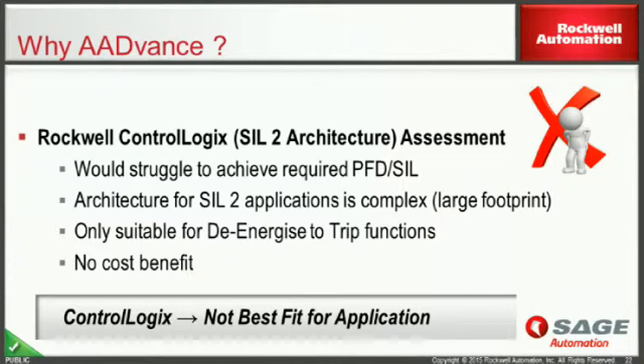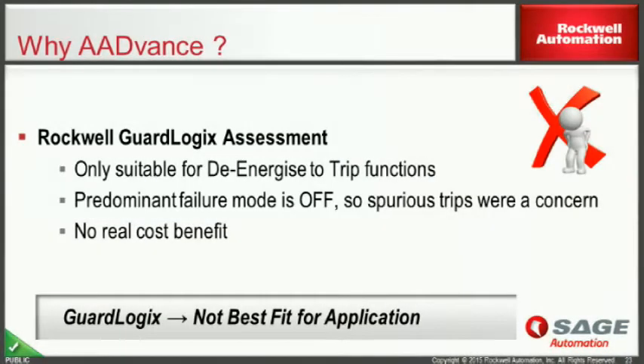And ControlLogix is only really suitable for de-energized to trip functions, and we have a couple of energized to trip functions within this system. So instead of failing to off, we needed to make sure that we maintained or energized a function to trigger a safety function. And there was no real cost benefit either in terms of hardware cost between AADvance and ControlLogix SIL2. The GuardLogix, again, it's only suitable for de-energized to trip functions, really is suitable for machine guarding.